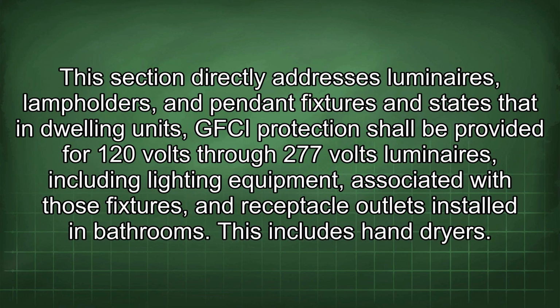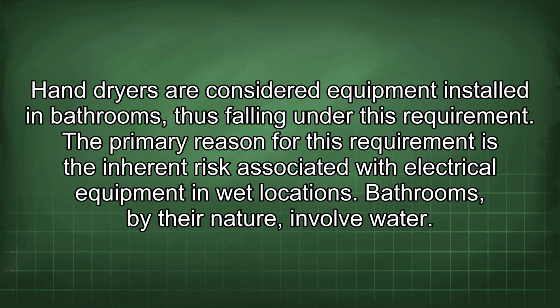This section directly addresses luminaires, lamp holders, and pendant fixtures and states that in dwelling units, GFCI protection shall be provided for 120 volts through 277 volts luminaires, including lighting equipment associated with these fixtures, and receptacle outlets installed in bathrooms. This includes hand dryers. Hand dryers are considered equipment installed in bathrooms, thus falling under this requirement.